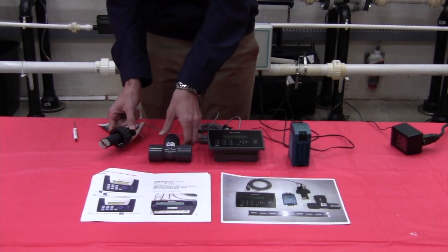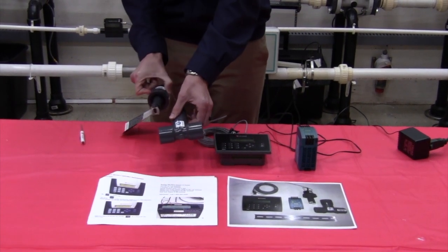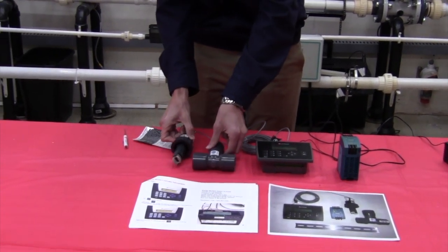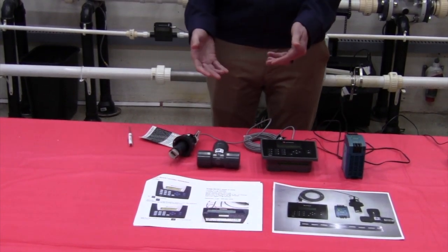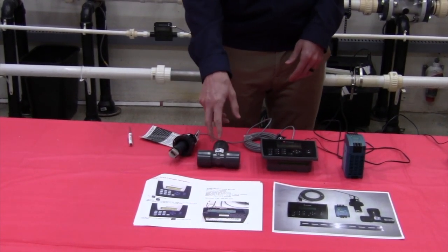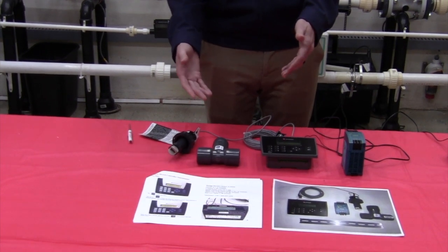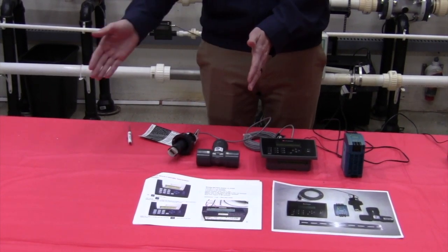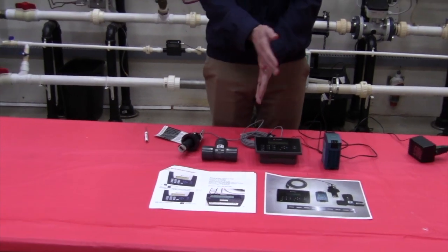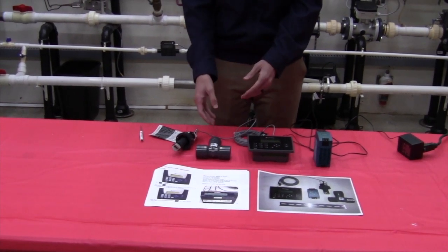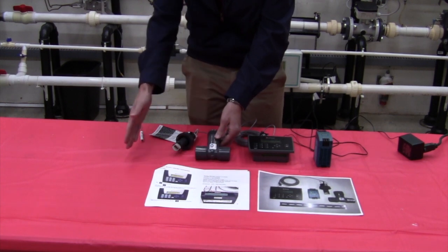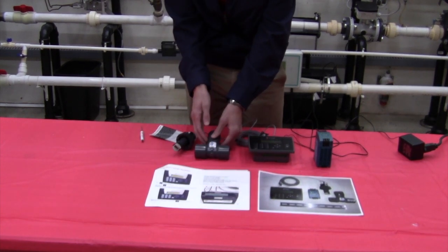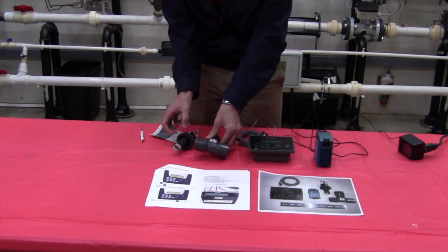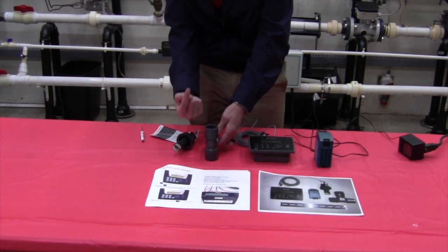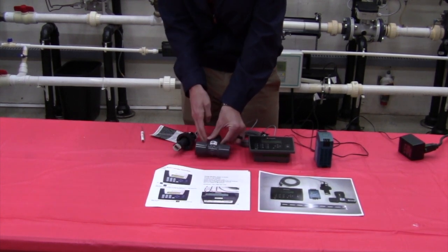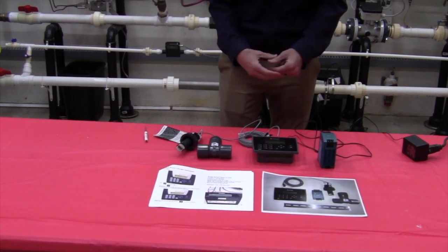I did want to mention the flow meter itself, when it installs in the T at your fill station. For best accuracy, if we're in a 1-inch pipe, we want 10 pipe diameters upstream of the flow meter and 5 pipe diameters downstream. So in a 1-inch pipe, we would want 10 inches up, 5 inches down. We would also prefer to have this installed in a vertical orientation with flow up. That is the best case scenario for accuracy.